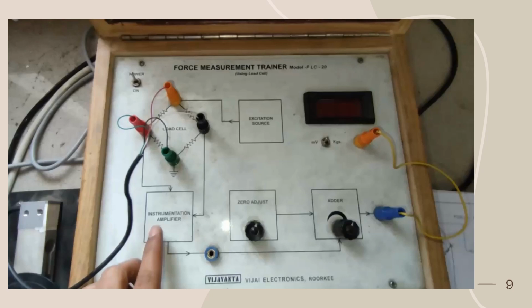And then we have zero adjust. Zero adjust is used to calibrate the actual zero weight to the value 0 on the machine. For example, if no weight is applied on the cantilever beam and we get some positive value like 0.01 or 0.02 kg corresponding to no weight, then we use the zero adjustment. We move it clockwise or anti-clockwise accordingly to adjust the reading to 0, so we can get precise and accurate readings.